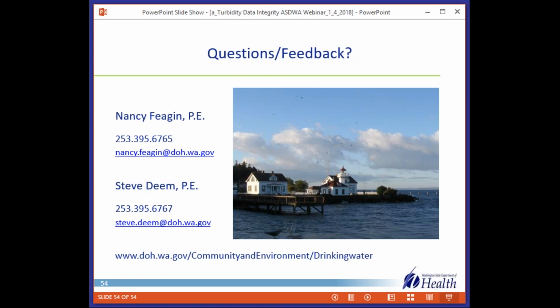So for example, if someone was visiting your plant, you were giving them a tour and they ran into the turbidity sensor and it caused a spike, well, that's not a real spike. So that one you would document in an excursion log and you would not report that as a regulatory value. But you need to be really careful that you really are just excluding the ones that are not true readings.